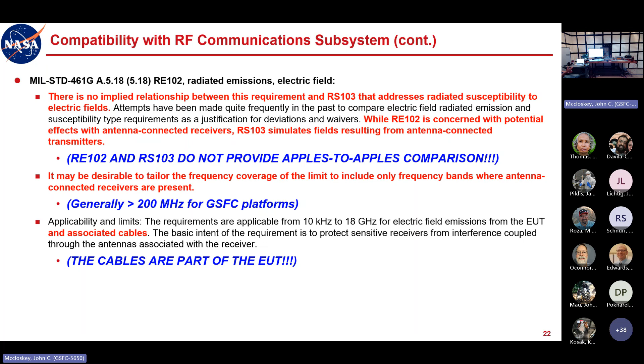So the requirements are applicable from 10 kilohertz to 18 gigahertz, this is RE102 specifically, for emissions from the EUT and associated cables. That's a very important phrase there, which is why I highlighted it. The cables are part of the EUT, EUT being equipment under test. That's, again, nomenclature, right? So talking a little bit more about that, when you're doing component or subsystem level or instrument level EMI testing, this shows the general EMI setup diagram per GEVS. It's tailored for MIL-STD-461G.